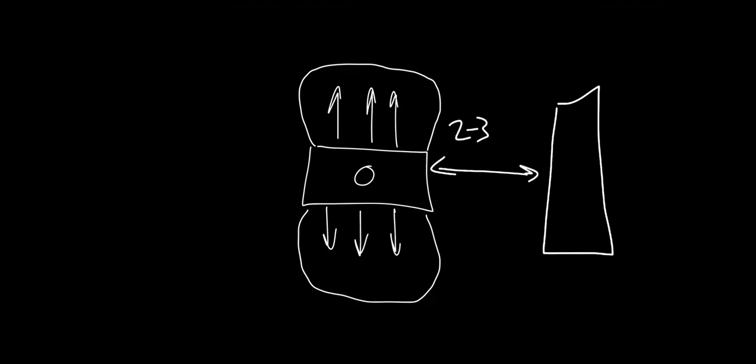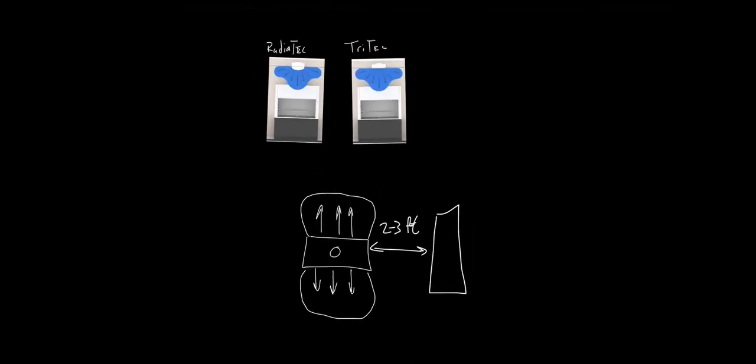This allows them to be placed relatively close to fume hoods. However, they should be placed at least 2 to 3 feet away from the face of the hood, and they should always be located such that their throw pattern is parallel to the face of the fume hood as shown here.